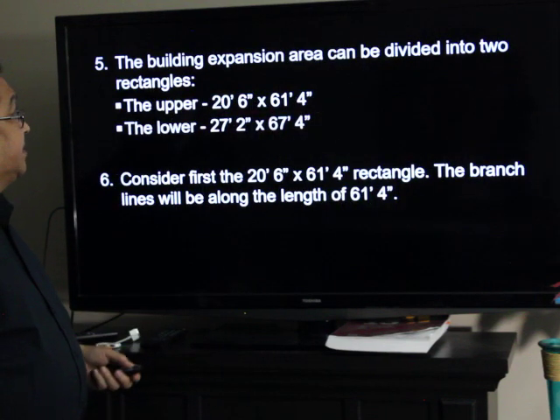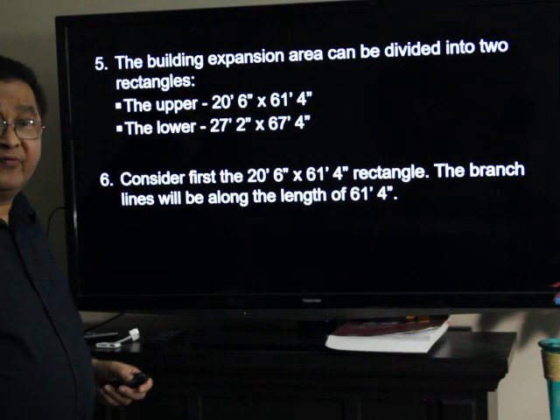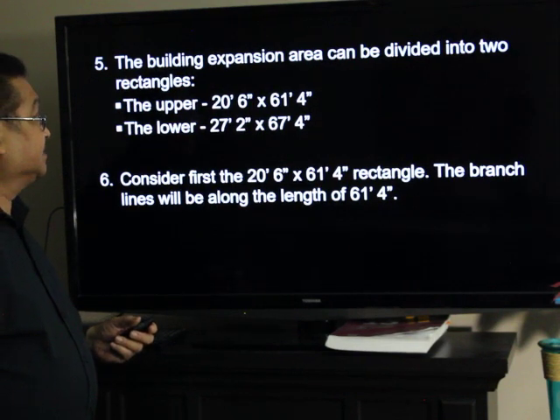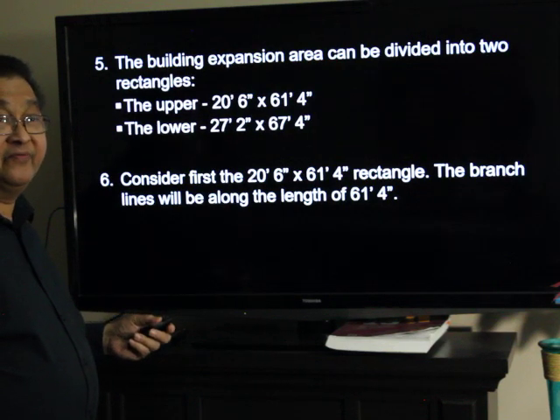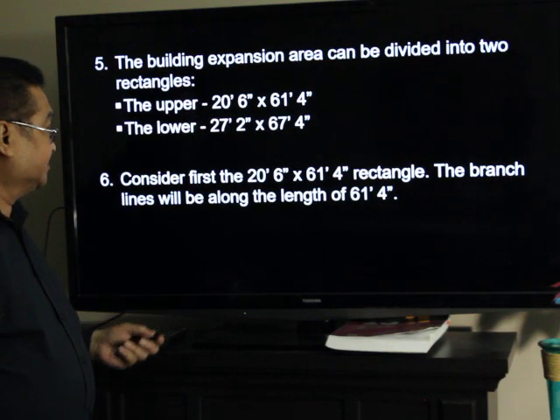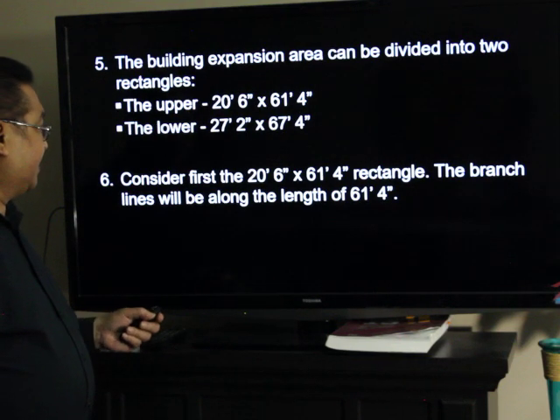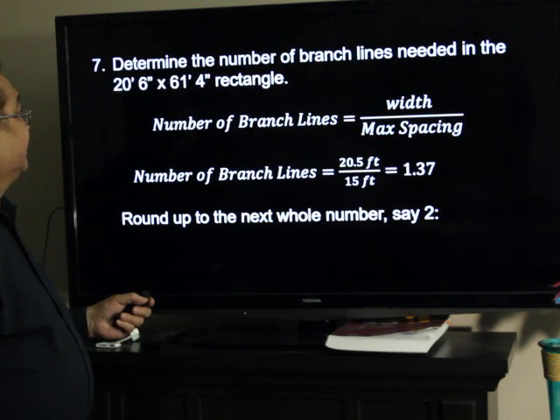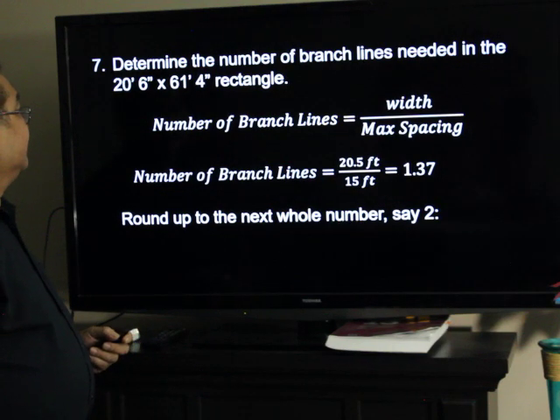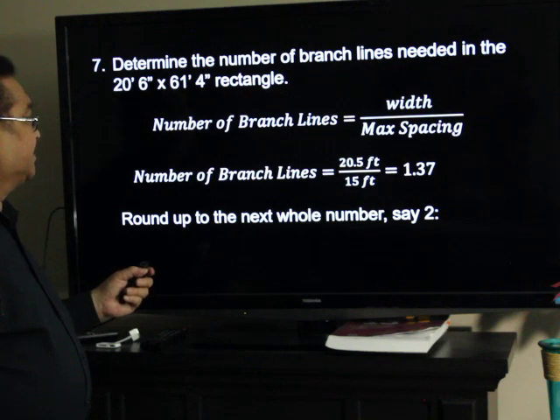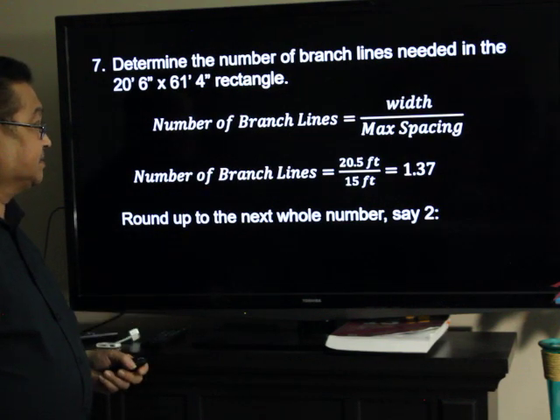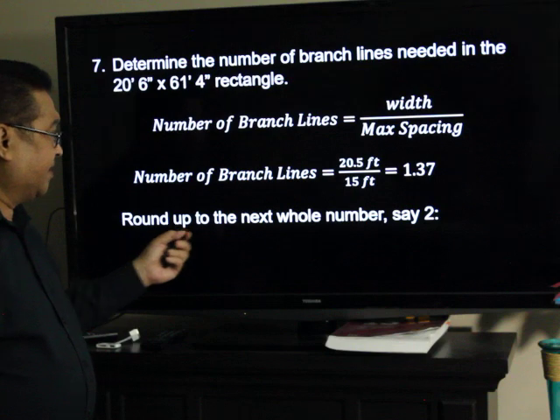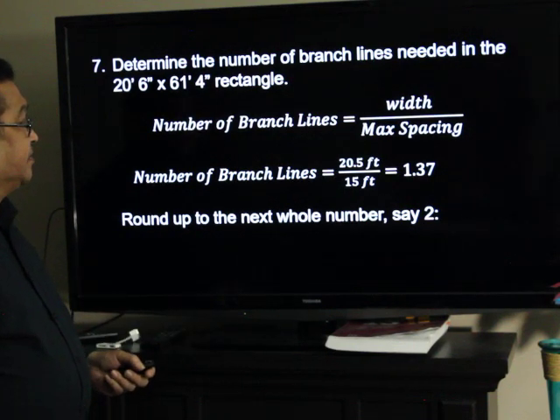So, the building expansion area can be divided into two rectangles for ease in analysis. The first one is the upper, which is 20½ feet by 61 feet 4 inches. And the lower one is 27 feet 2 inches by 67 feet 4 inches. Consider first the upper rectangle. The branch lines will be along the length of 61 feet 4 inches. The number of branch lines will be its width divided by the maximum spacing: 20.5 divided by 15 feet, we have 1.37 — round up to the next whole number, we have 2 branch lines.